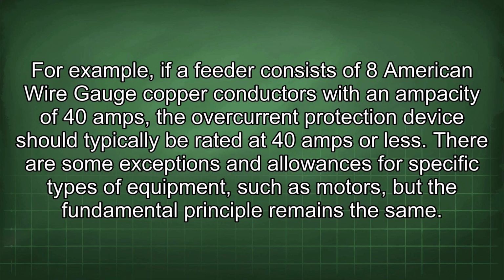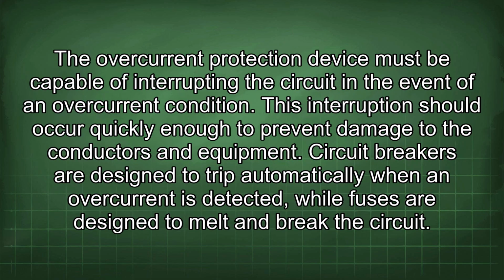For example, if a feeder consists of 8 American wire gauge copper conductors with an ampacity of 40 amps, the overcurrent protection device should typically be rated at 40 amps or less. There are some exceptions and allowances for specific types of equipment, such as motors, but the fundamental principle remains the same. The overcurrent protection device must be capable of interrupting the circuit in the event of an overcurrent condition. This interruption should occur quickly enough to prevent damage to the conductors and equipment.